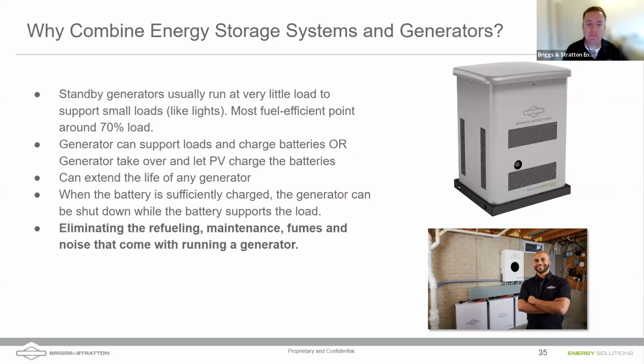All right, thank you. Standby generators — a lot of times, and we have in our GC 1031 controller on our generators, you can actually go in and look at what's known as a histogram. This histogram in the controller will tell you at what load point the generator has been run at in history, in its life. One thing that's unique — and I've seen this on some other generators too — is that a lot of times when we size these 26K generators or 18K generators, you notice that they're really running at like 20% load or 30% load.